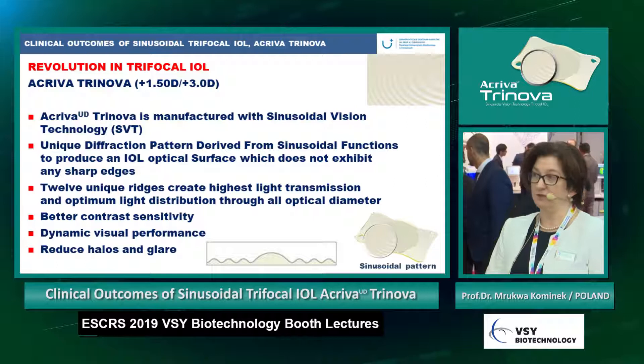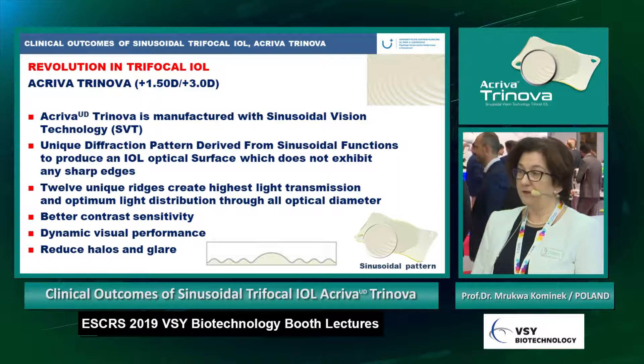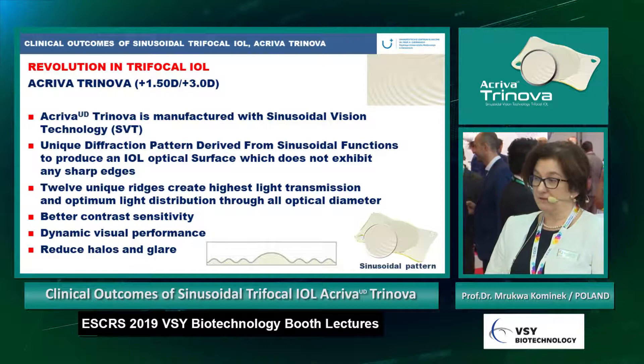Acriva Trinova is manufactured with sinusoidal vision technology. This is a unique diffraction pattern derived from sinusoidal functions to produce an IOL optical surface which does not exhibit any sharp edges. We find 12 unique ridges created for the highest light transmission and optimum light distribution through the full optical diameter.